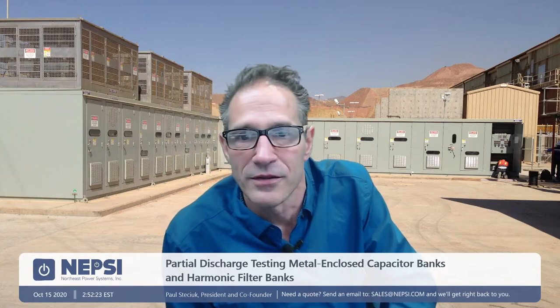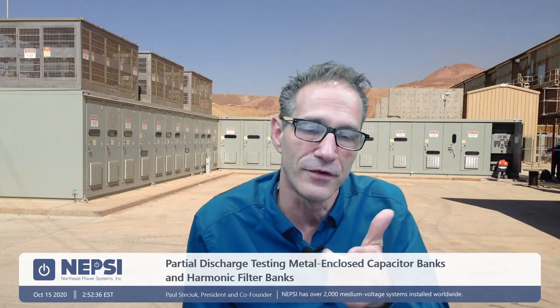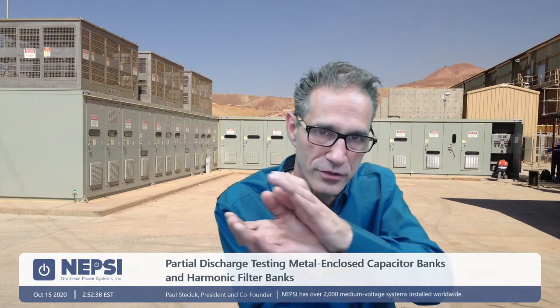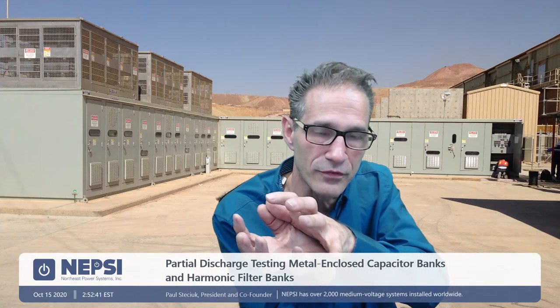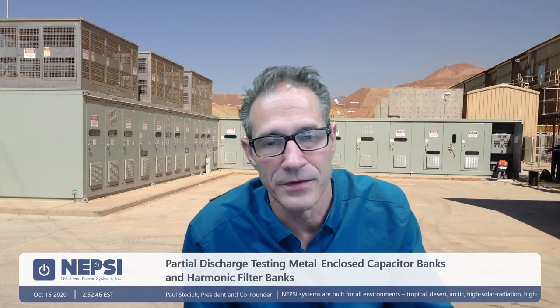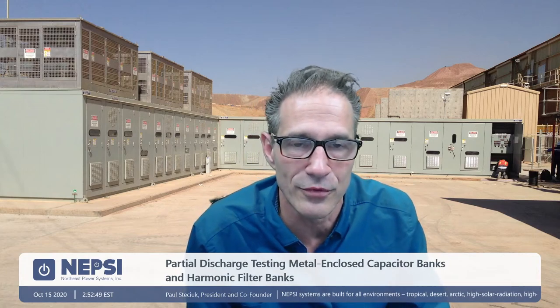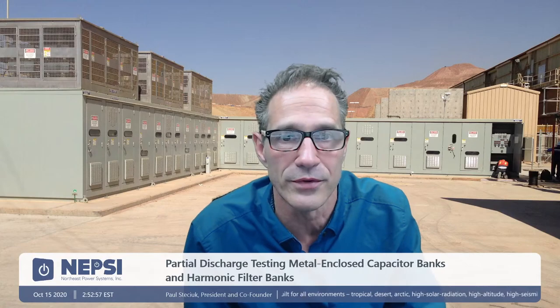Is there a way to locate the partial discharge? How do you locate where the partial discharge is in the equipment? It's very difficult when we do have partial discharge. It is kind of a go and hunt situation. They do have a device, which we do not have, like an antenna device that you can point into your equipment and listen for it. There is also turning out the lights and looking for a corona. That is another one. And then you get the audible sound to look for. For us, we generally will start to hunt and peck and search through the equipment and try to find where that partial discharge is occurring.